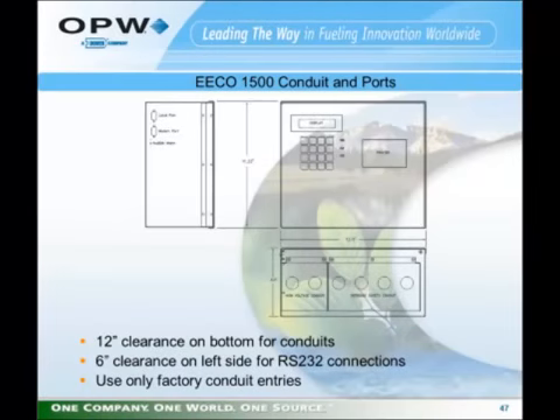EECO 1500 conduits and ports. On the bottom of the EECO 1500 are the conduit entry points. If you look at that, the left 2 are for high voltage, the right 4 are for low voltage or intrinsically safe circuits. We recommend 12-inch clearance on the bottom of the unit for conduit access, and 6-inch clearance on the left side for access to the 2 built-in 9-pin RS-232 communications ports. You're to use only the factory conduit entries. Any other holes that are drilled in the chassis will result in loss of any remaining warranty on the unit.